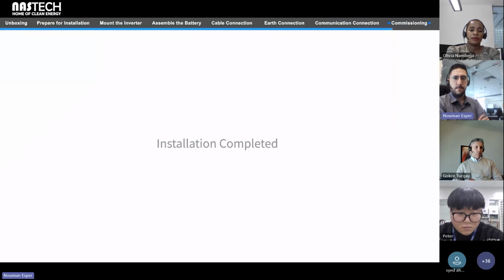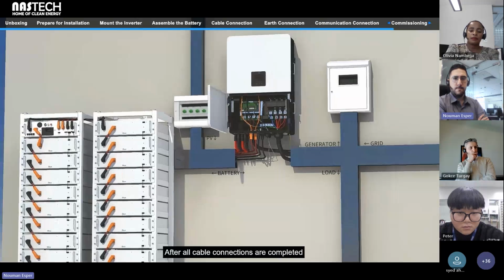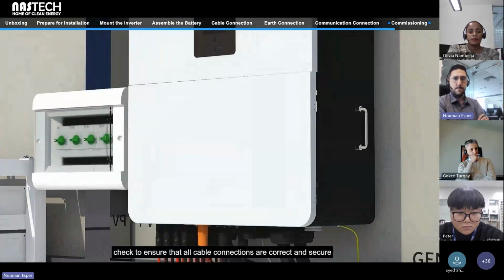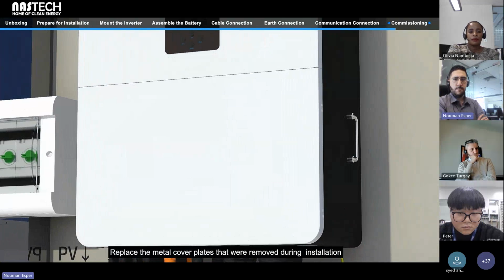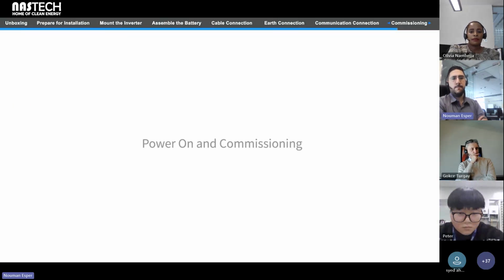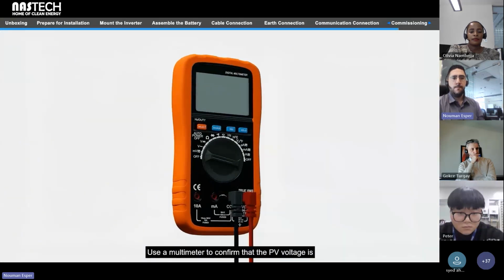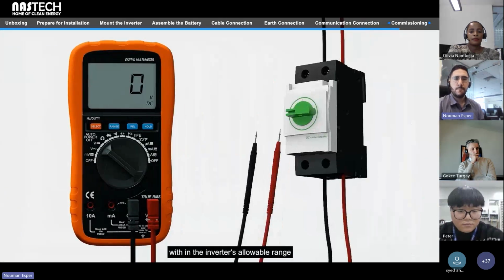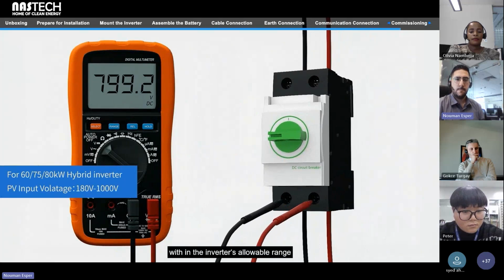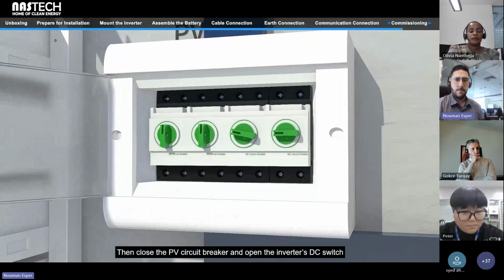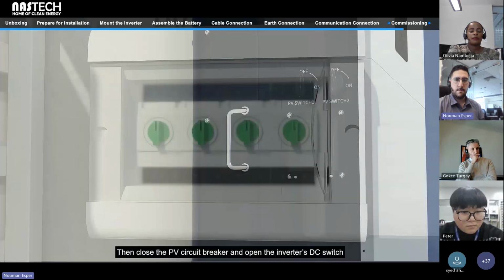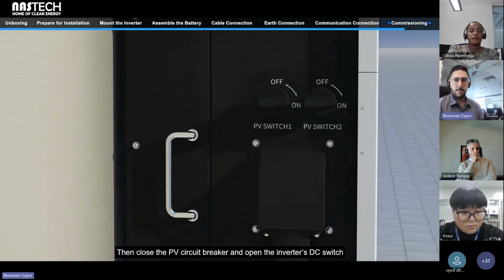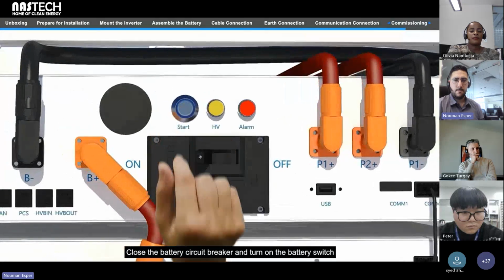Installation completed. After all cable connections are completed, check to ensure that all cable connections are correct and secure. Replace the metal cover plates that were removed during installation. Power on and commissioning. Use a multimeter to confirm that the PV voltage is within the inverter's allowable range. Then close the PV circuit breaker and open the inverter's DC switch. Close the battery circuit breaker and turn on the battery switch.